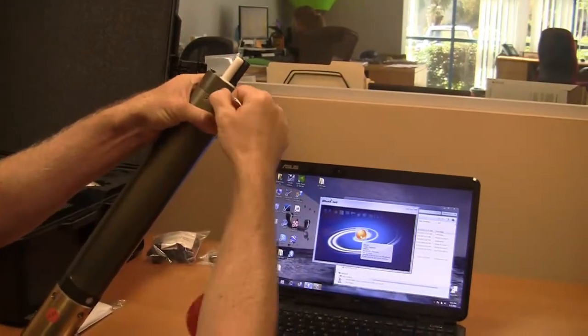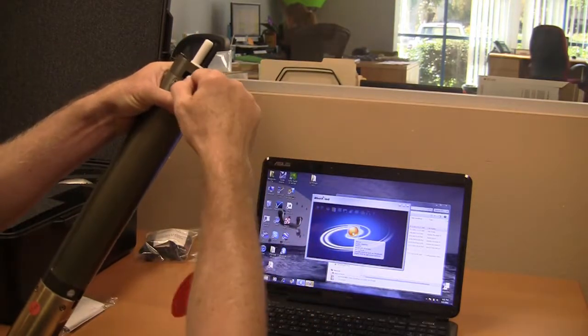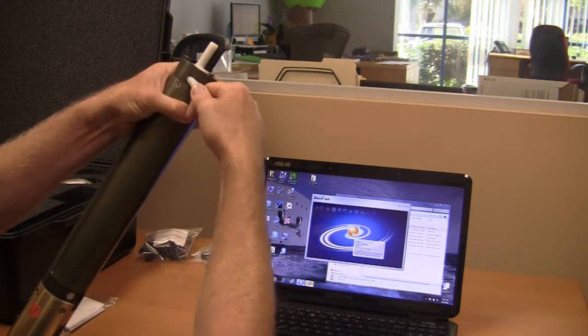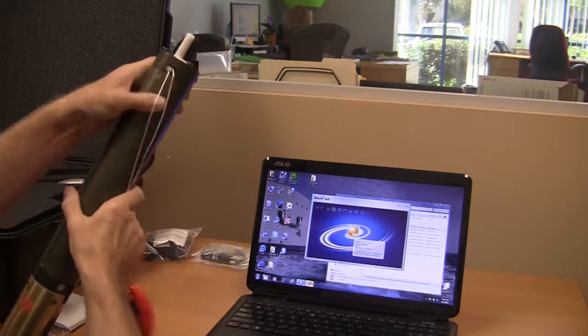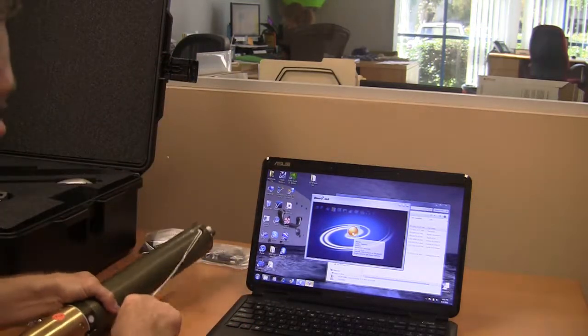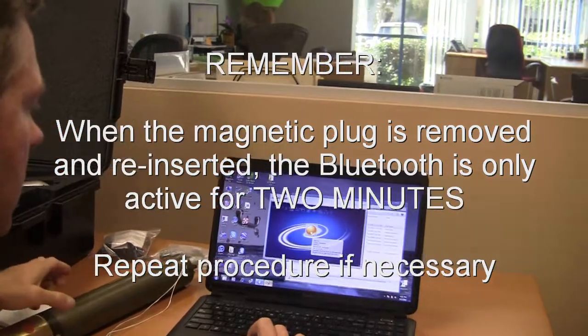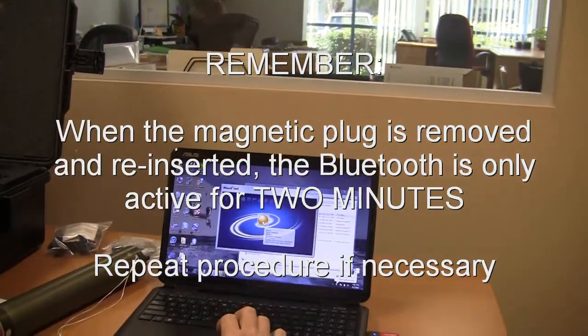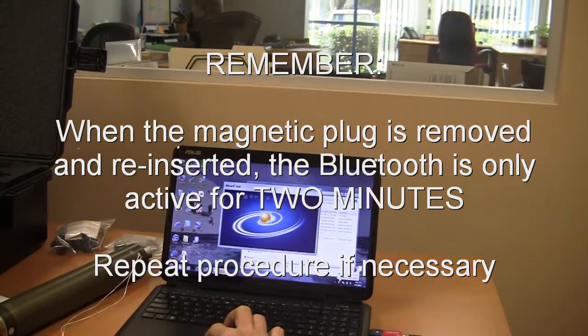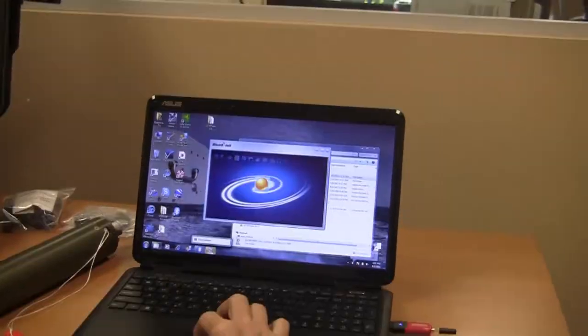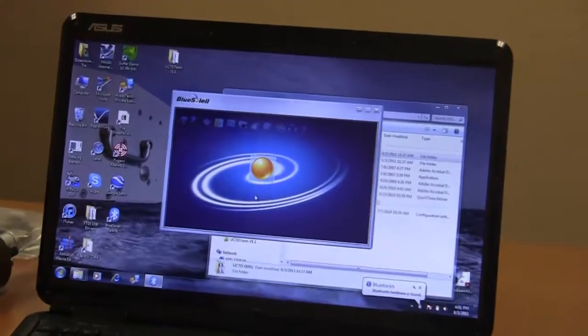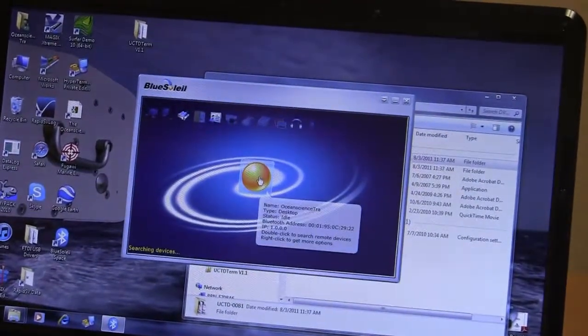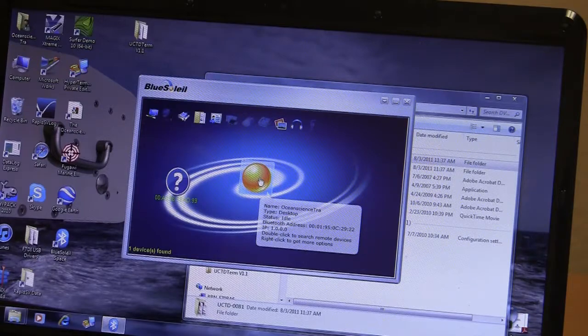You have to cycle the plug, pulling it out and reinserting it. After reinserting the plug, Bluetooth is active for two minutes on the probe. It's good to remember that after two minutes the Bluetooth is going to get turned off. Now the Bluetooth is looking around for devices.